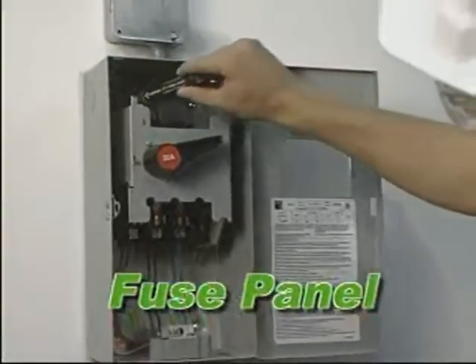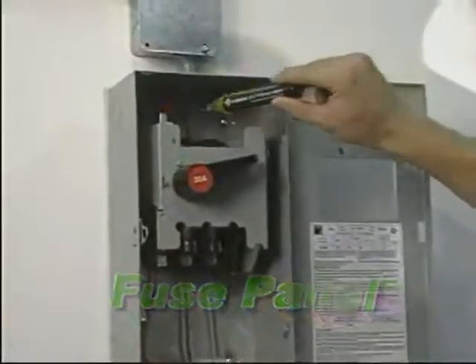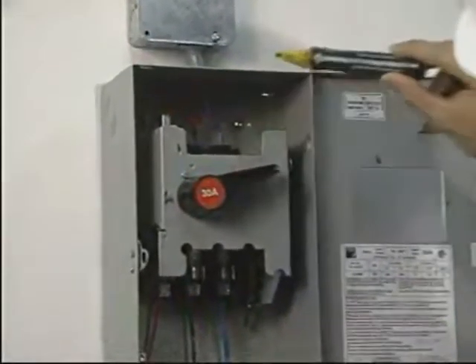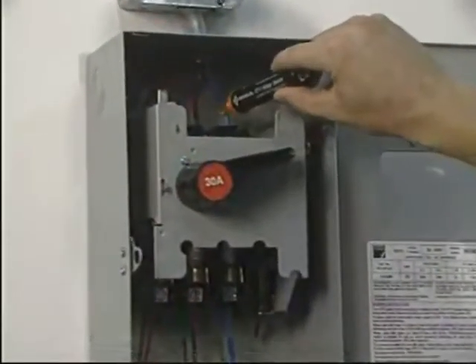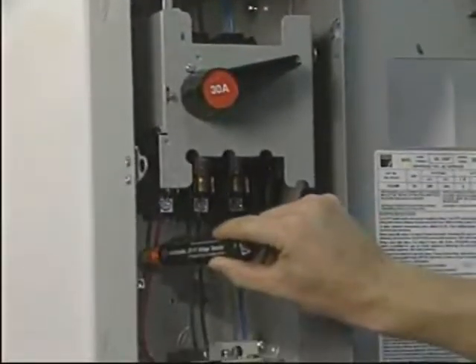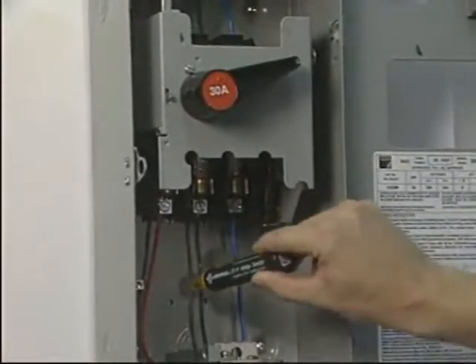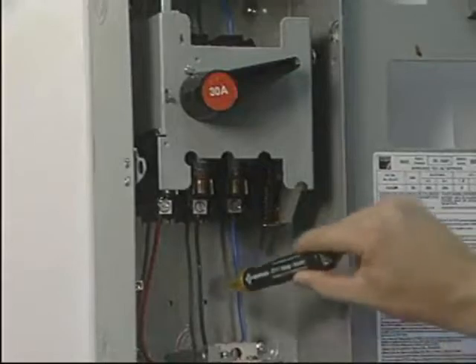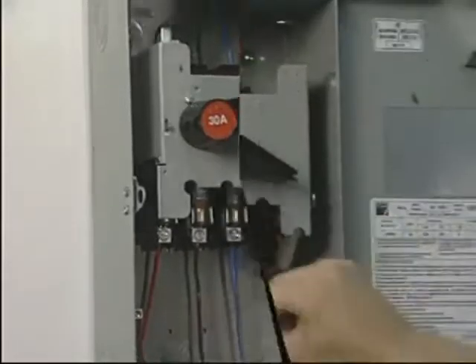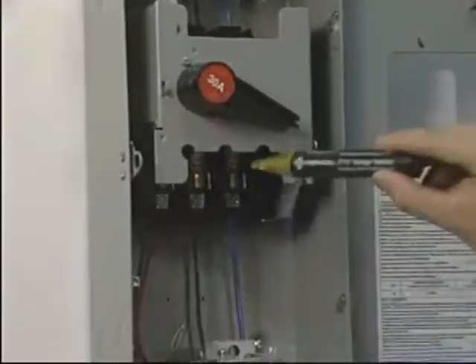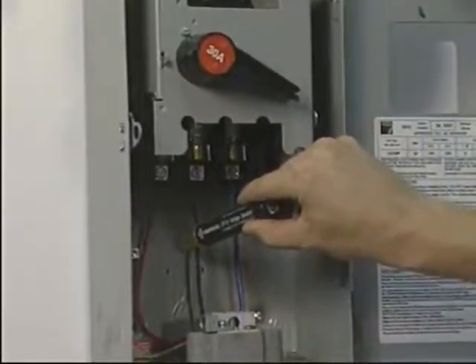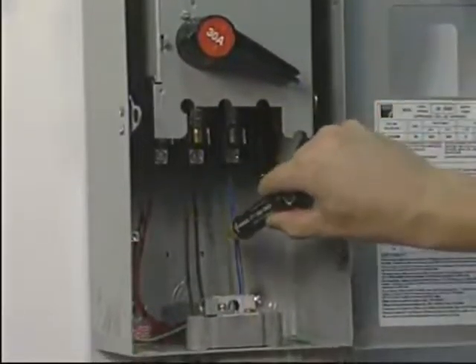When testing a disconnect with a fuse, check the line side of each phase one at a time. You should get an audible and visual alarm on each phase. Check the load side of each phase. If the fuses are okay, you should get an audible and visual alarm. If the disconnect is off or the fuses are defective, you should get no alarm indication.